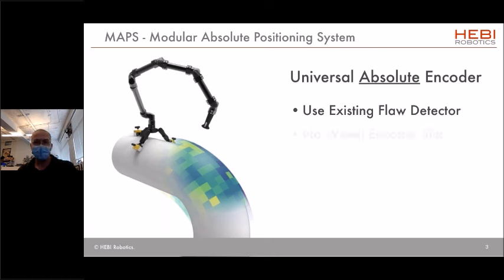There's no wheel encoders to slip, so the whole arm operates by basically clamping a base somewhere in space, and then once you've clamped that and registered your surface, you know where your probe is at all times, within a bounded amount of accuracy. With wheel encoders, if they slip, you technically now have no idea where your probe is. So you're reliant on the operator and the equipment to be very, very consistent in the field, and you really have no observability after the fact as to whether or not the probe was really where you thought it was.